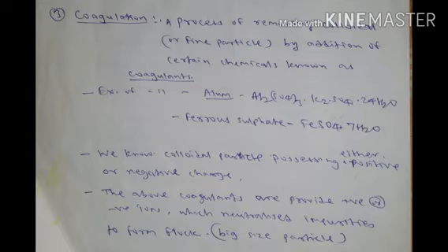So these ions react with colloidal particles, so that the colloidal particles become bigger in size, which is called a floc. Due to the increased size, they can be easily removed by the sedimentation process again, because colloidal particles do not settle down and they are charged particles, so it is very difficult to remove them by the sedimentation process alone. But with the help of the coagulation process, yes, we can remove them easily.